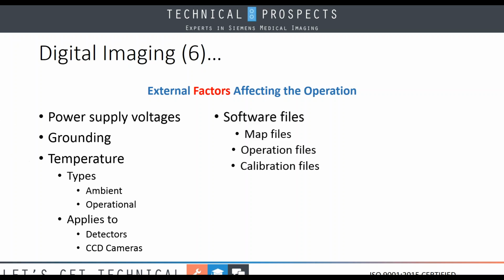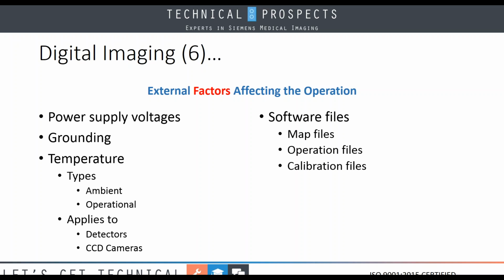Some other external factors are software files. Of these files, I'm really going to emphasize two: your map files and your calibration files. One, you need to ensure that the map file is proper for either your camera or the detector. Map files are typically ones that identify defective pixels at the time of manufacture. Calibration files are ones that do updates and also give us different levels of calibration. So these files, designed by the manufacturer, are used by the processing software to ensure that we get good quality images, and they can compensate for what is known to be defective.